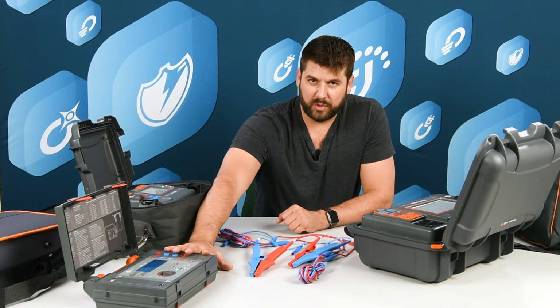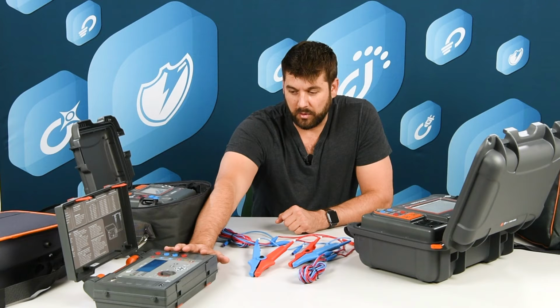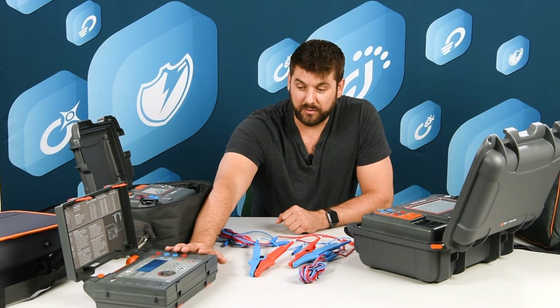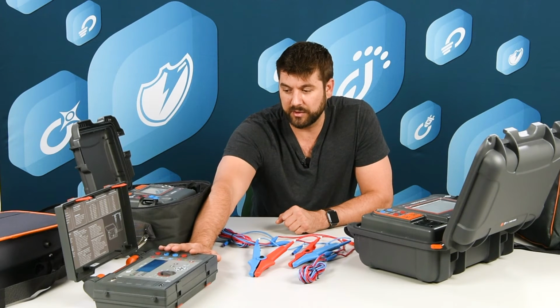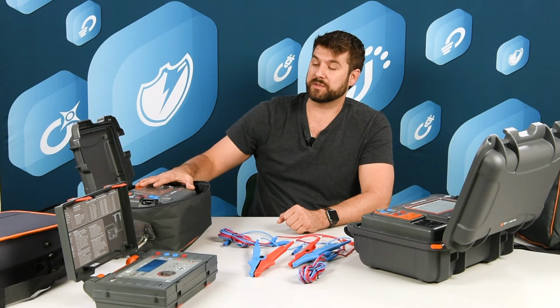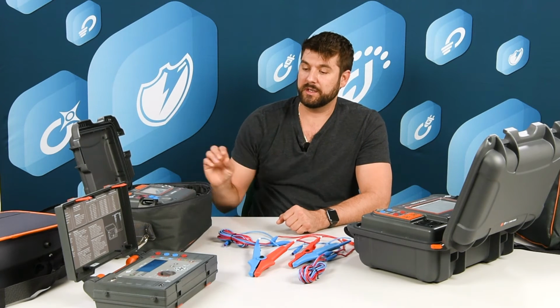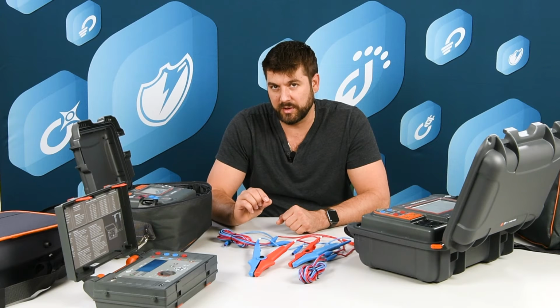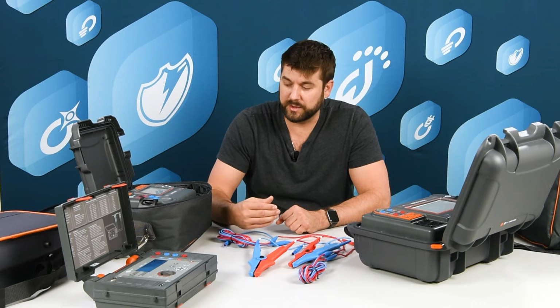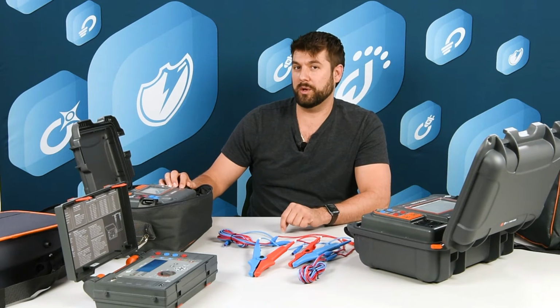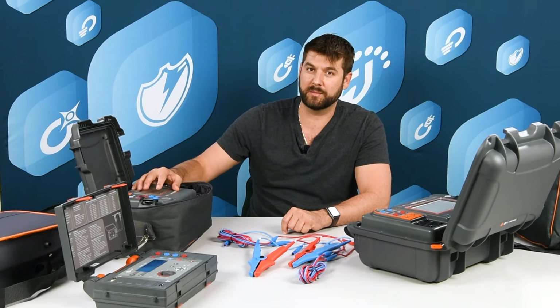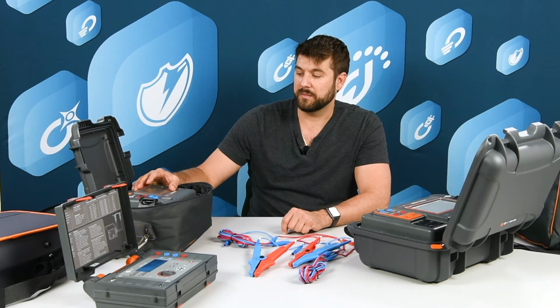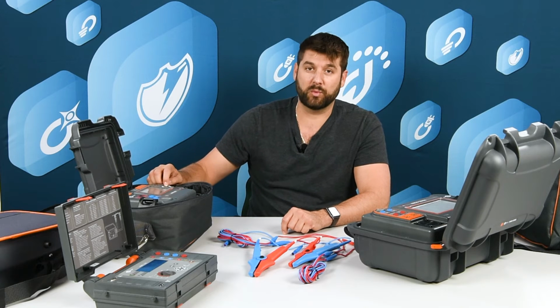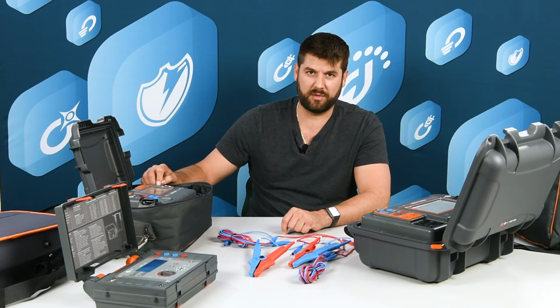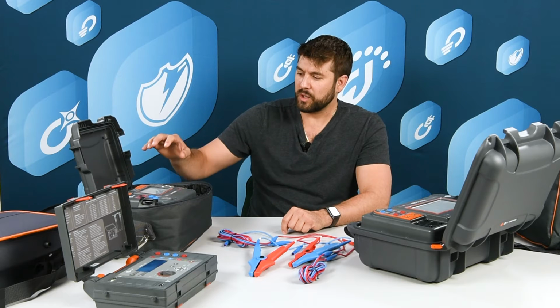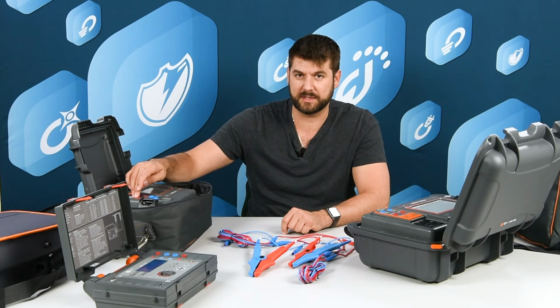The old one here, the MMR620, is going to give us 1 microohm of resolution, which is quite good for a fairly inexpensive microohmmeter. When we get up to the MMR650, the newer version, it's a much more precise voltage measurement, and thus the increased cost, but that allows us to measure to 0.1 microohm. So this is going to have 10 times the resolution. So this is 0.1 microohm, so that's 1/10 millionth of an ohm. But again, the test current is limited to 10 amps.